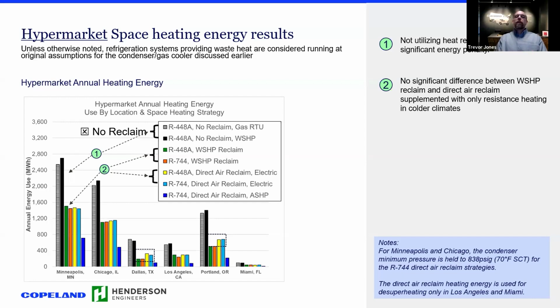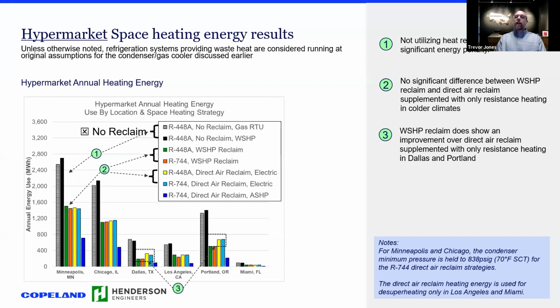where we see the real benefit is in more moderate climates in their heating zones, Dallas and Portland. They don't get as cold as Chicago and Minneapolis, so they spend more time in that 25 to 40 degree zone, where you're doing much better on your heat reclaim with the water source heat pump system on the hypermarket.